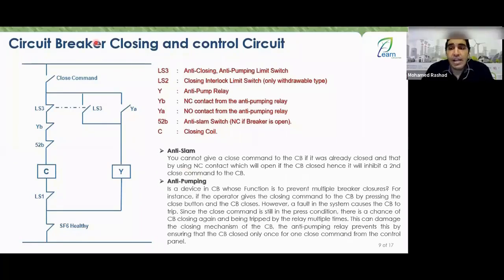All right, very good. So now I understand this entire circuit, and I have one last contact left. If my breaker is of the Schneider or ABB SF6 type, meaning it's not a vacuum circuit breaker, it would be an SF6 circuit breaker. SF6 circuit breaker or oil circuit breaker, my dear engineers. There is a gauge on the breaker. What does gauge mean, Engineer Rashad? It means meters, all right, or meters are in a gauge, engineers, on the breaker like this. Let me draw it for you like this.